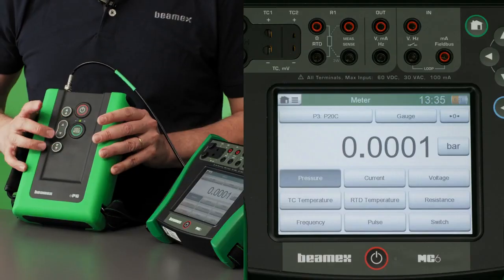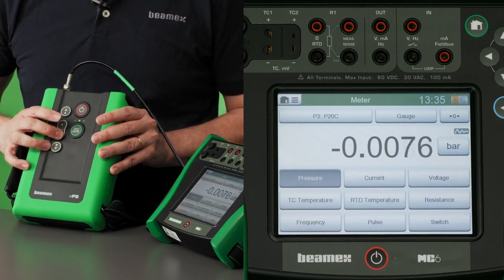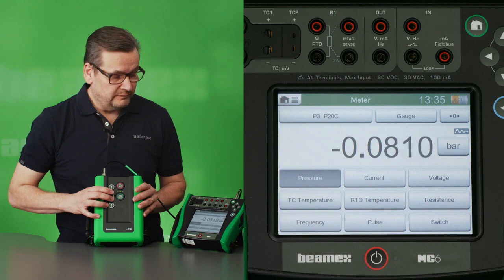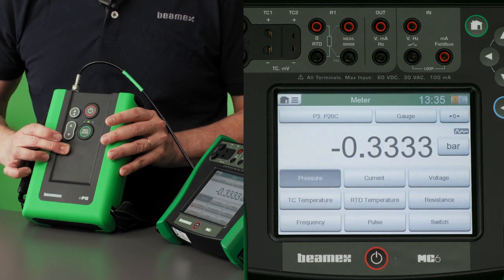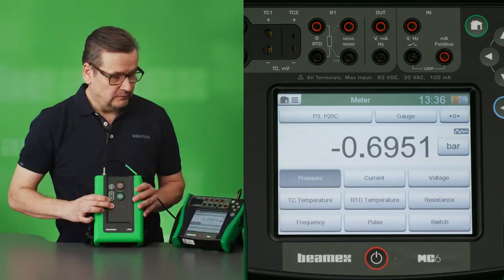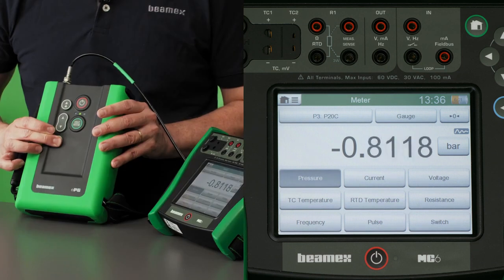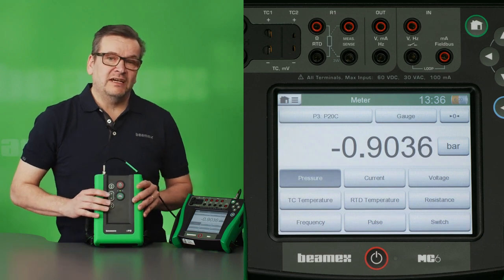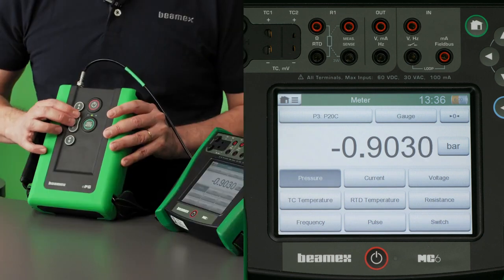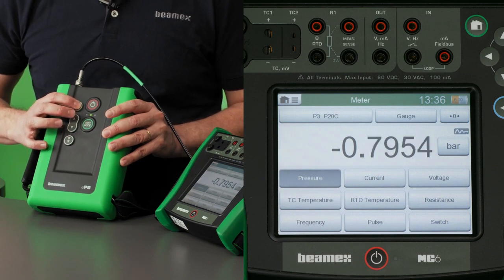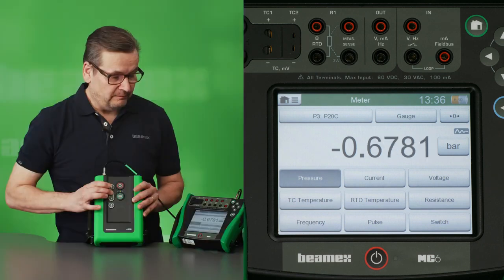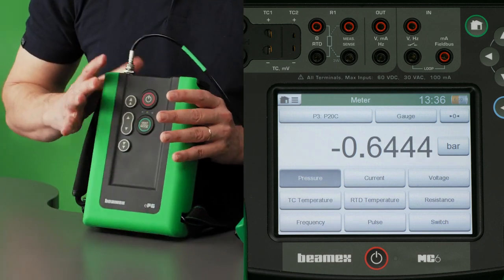Next, let's make some vacuum. Let's first make some fine adjustment with the small vacuum. And then hold the coarse button for more vacuum. ePG can go at least to 85% vacuum. Once we are down to vacuum, we can come up with the coarse adjustment or fine adjustment. And finally, vent the system to get back to 0.